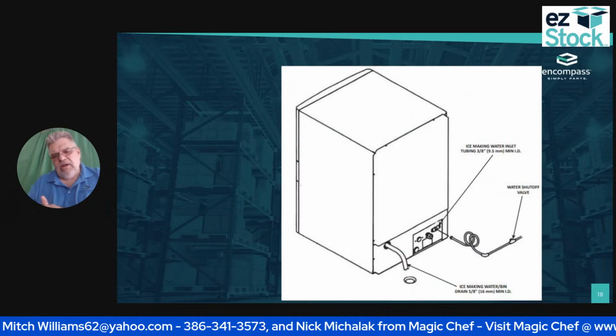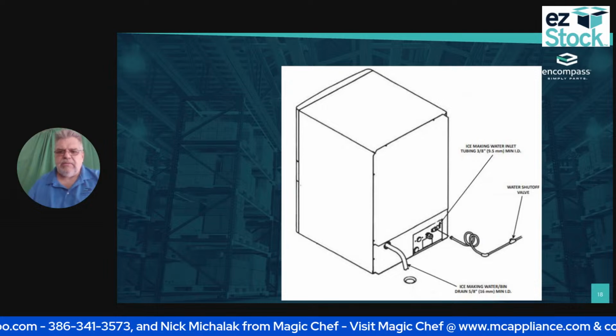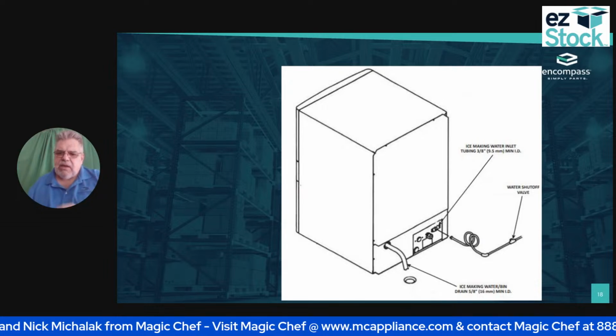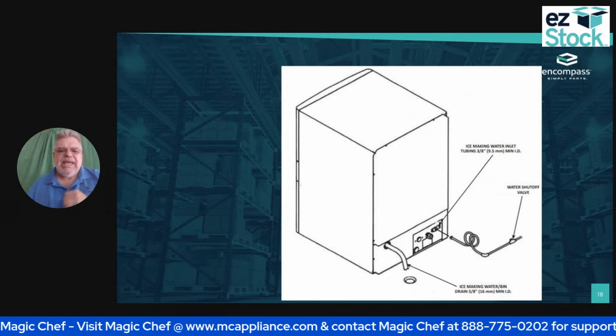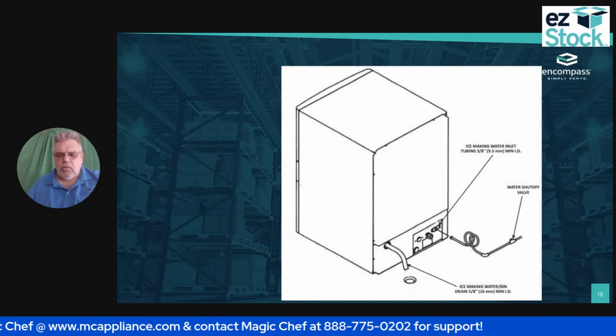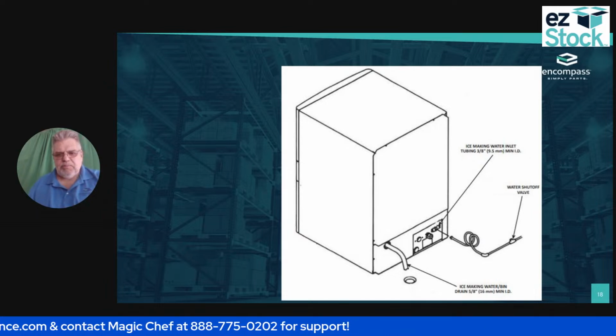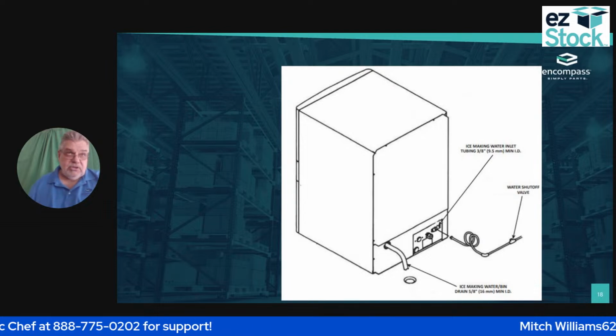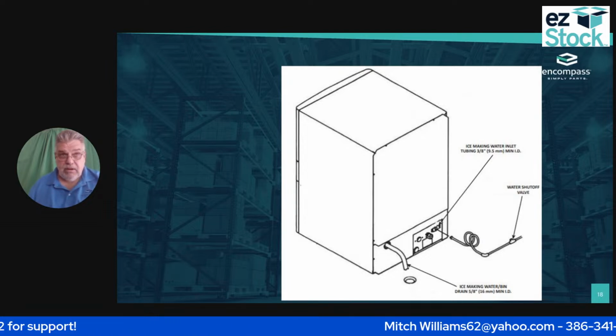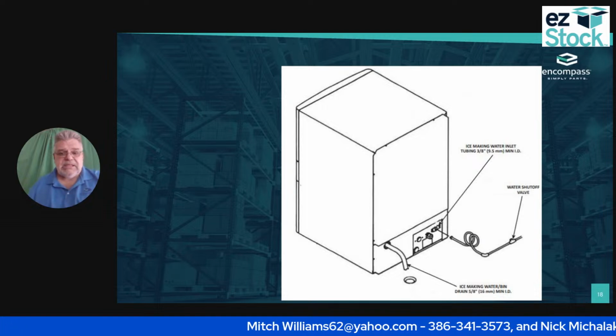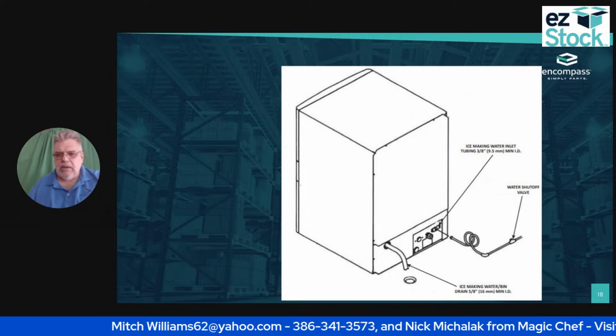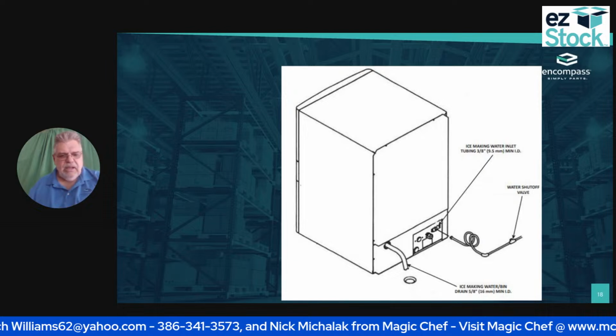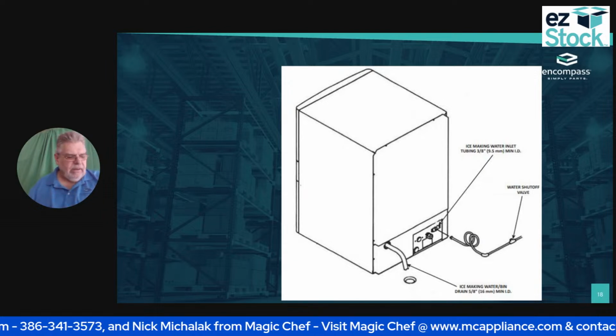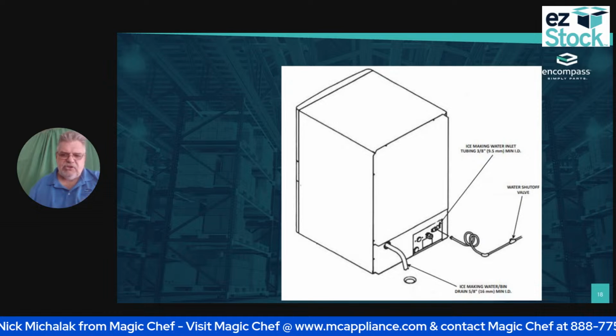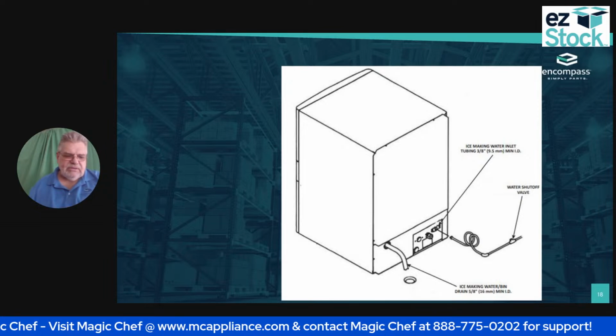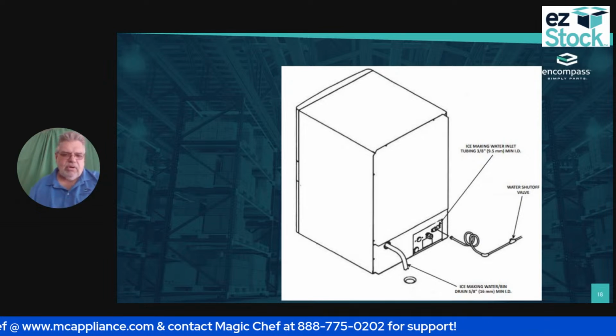Here is a picture of the back of this unit, okay? If you notice, the ice making water inlet tubing is 3/8. It needs to be 3/8. Don't put a 1/4 inch line on it. There are people that try to run a 1/4 inch line just like it's on the back of your refrigerator at home. That needs to be at least 3/8. Okay. And then I need a water shut off for that. The problem is 9 times out of 10, if I'm not the guy that installed it, I don't think about the water valve shut off, and I may or may not have a water shut off.